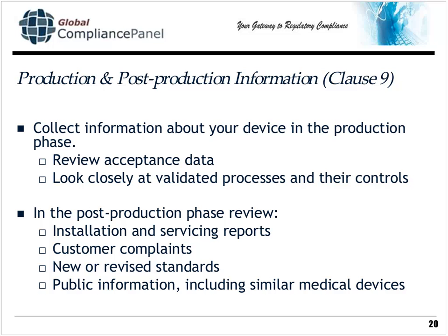For post-production, you want to look in a couple of other areas. Installation and servicing. So if you install the device or you service the device, then you're going to generate installation reports and service reports. What's going on? Are we identifying potential risks? Are we finding nonconformities? You have to have a system of complaints in both QSR and 13485. So you need to evaluate every complaint, or at least some kind of analysis of the complaints, against the requirements that you set in the risk management project, to make sure that you are not seeing complaints demonstrating that the risk that you estimated is not being achieved, that in fact it's worse.